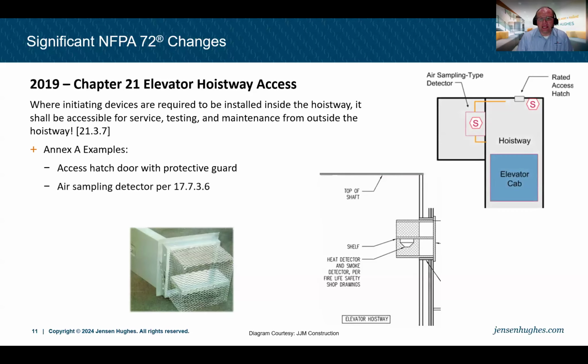Another example might be using an air sampling or a linear heat detection system where the detector is really located outside the hoistway. The piping goes inside the hoistway, and so there's nothing to service inside the hoistway. We simply can test the unit from outside that hoistway if it's properly installed. That might be another very nice way of doing that, providing the protection necessary, but also protecting the inspector. And linear heat detection, as I said, with the connection points outside the hoistway, so we can still do the testing and keeping our inspectors safe outside the hoistway.